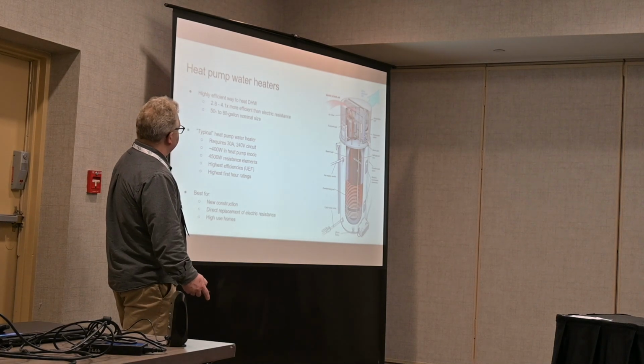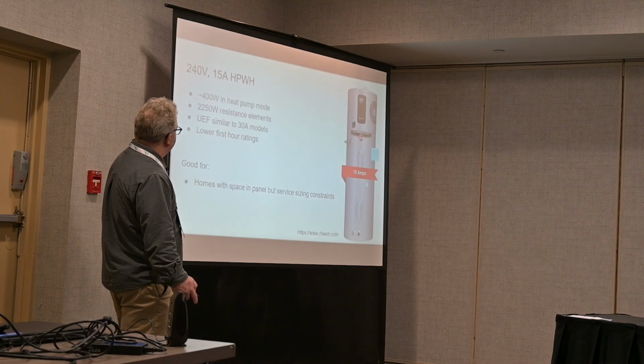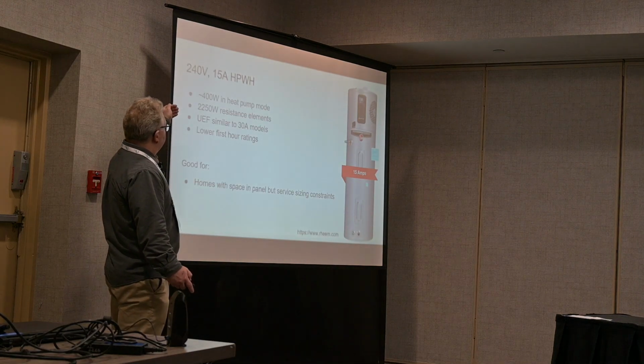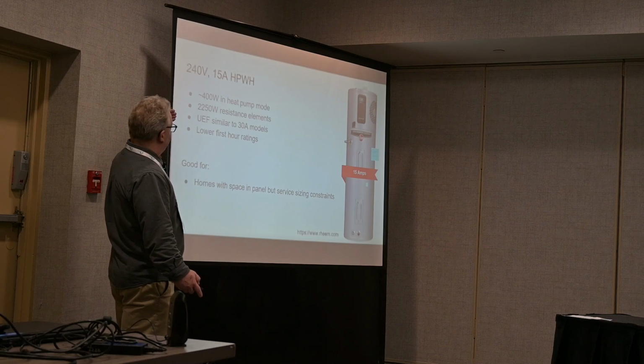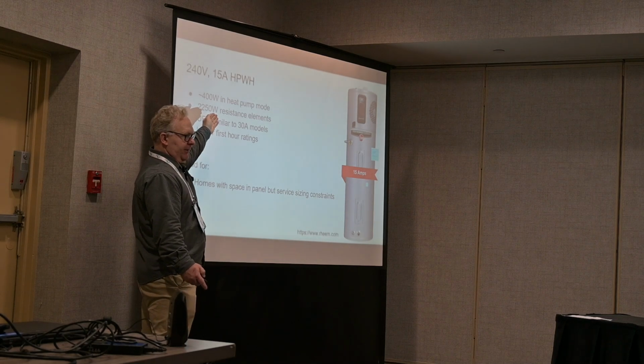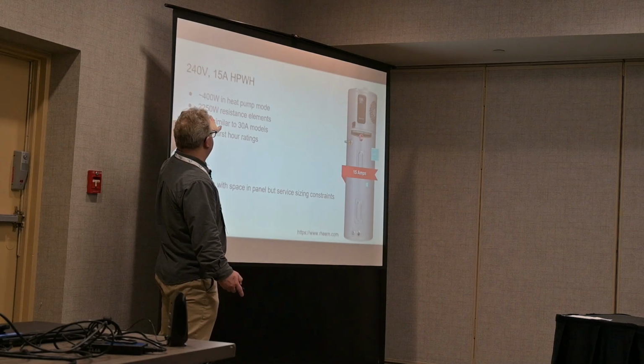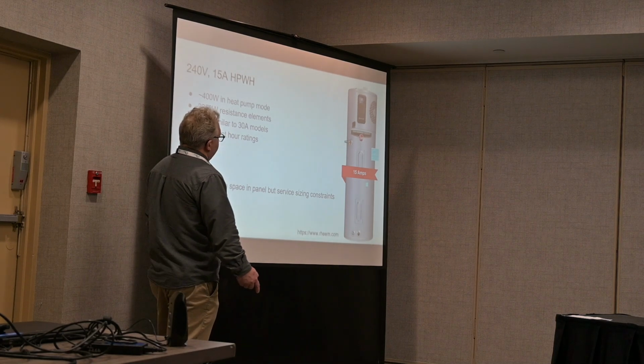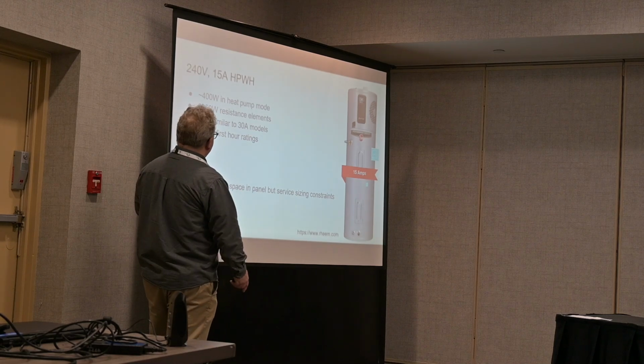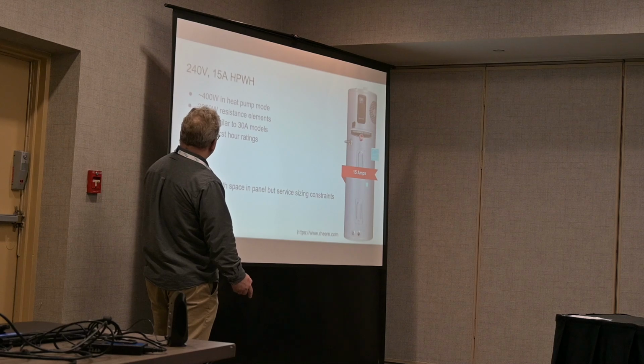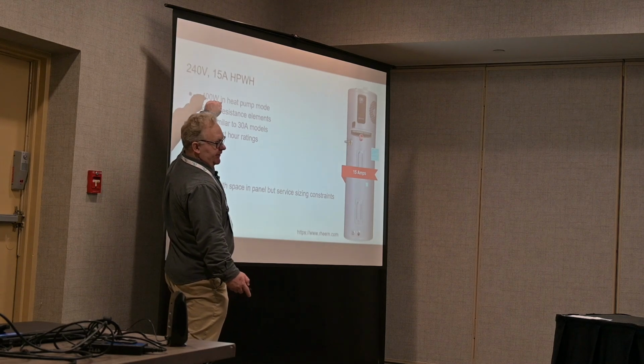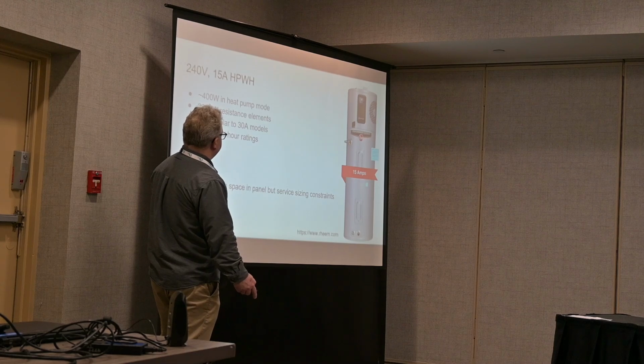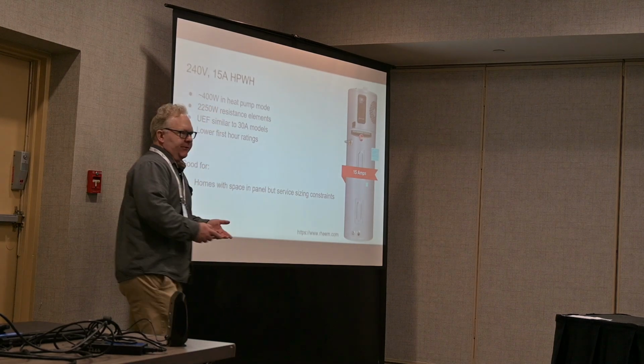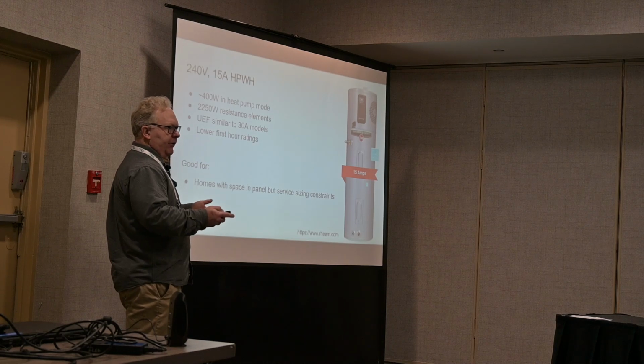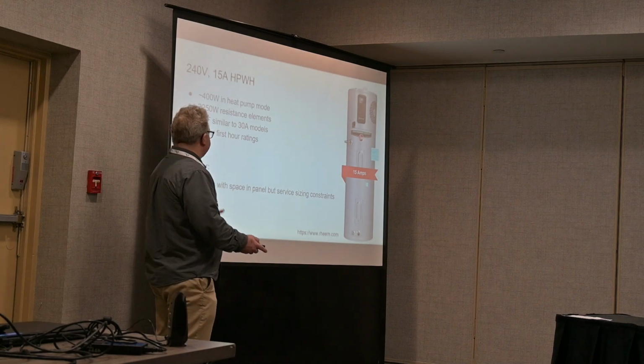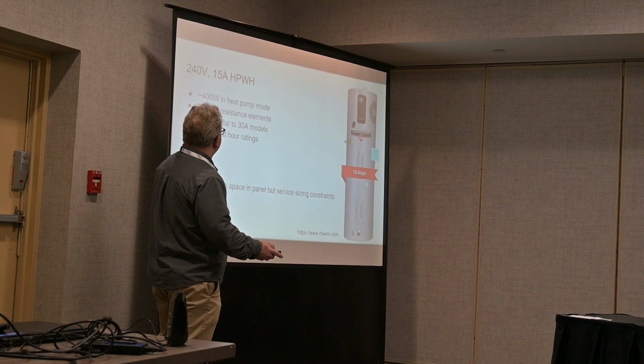But if your capacities just don't work for that, there are 240 volt water heaters that have smaller resistance elements. You've now cut the size of the resistance element in half, and so that'll add less load to your panel. They typically have the same compressor as the 30 amp models. So if the house has lower hot water requirements, this may be an option.